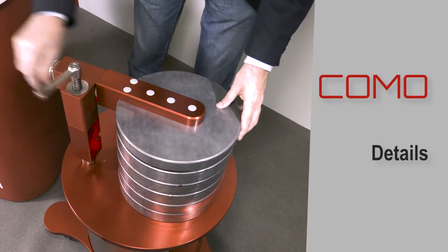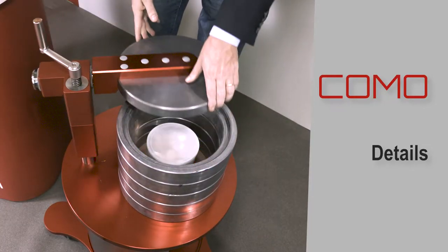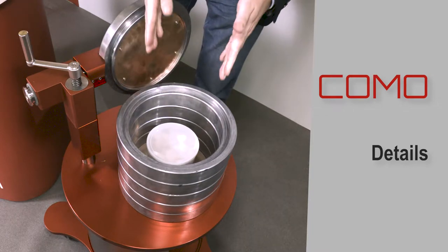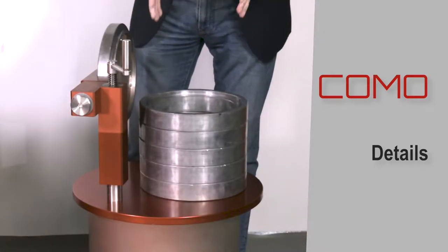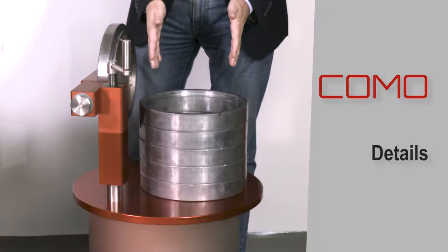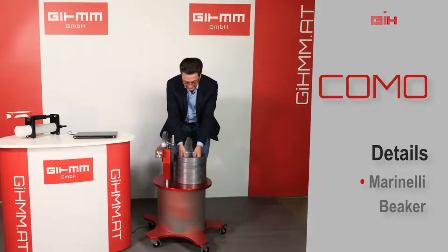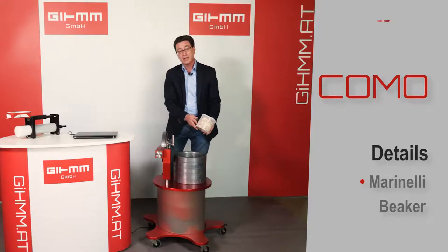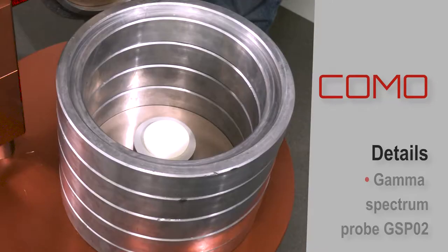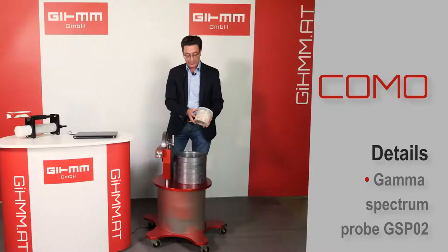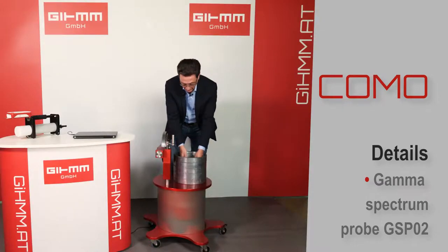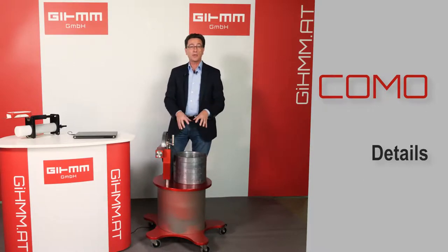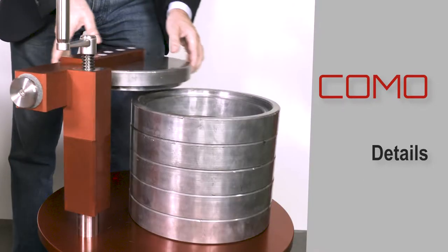With the crank, very simply, we open the cover of our lead shield, shuffle it over, put it up, and now we have full access to the inside of our measuring chamber. Inside, I just have here our Marinelli beaker with mushroom samples, which we want to measure. Underneath, I see the top of the gamma spectrum probe, GSP02, and to measure, we simply place the Marinelli beaker on top of our probe and close the lead chamber.